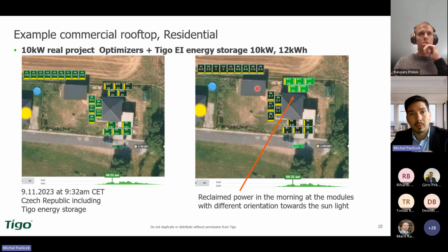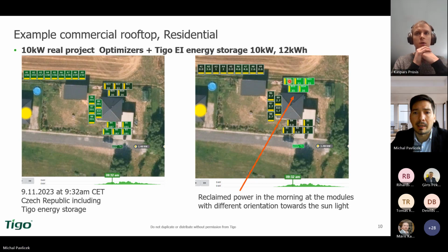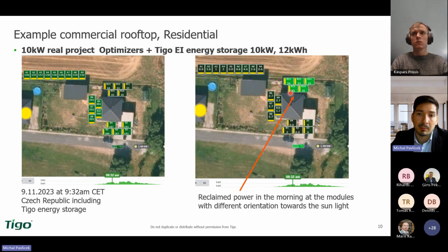So the power which in addition produce the optimizer. So you may see here on those modules which are oriented towards the sun, there is no need at this moment too much to optimize. Of course, some small needs are, but not big. While the modules on the backside are having all the power from optimization. So if the optimizers wouldn't be installed, these modules wouldn't produce any power because they are oriented to the shade on the north side.